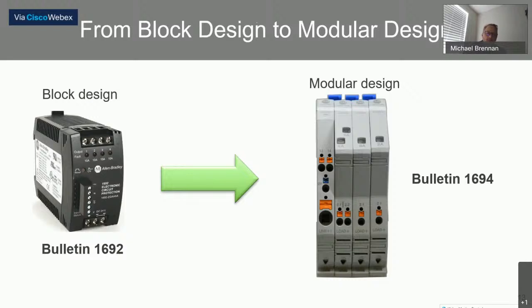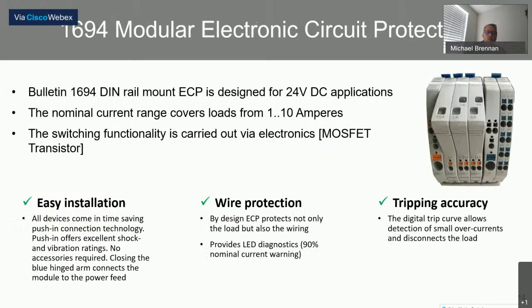So what is the difference between a block design and a modular design? Well, on the left, the 1692 that we were talking about, that's the block design. On the right is a brand new 1694 product, which is a modular design. And what this allows for us, we'll talk a little bit about. So what is the 1694? Again, this is specific to 24-volt DC applications. The 1694 is a DIN rail mount electronic circuit protector that allows you to choose the number of circuits that you want to use.